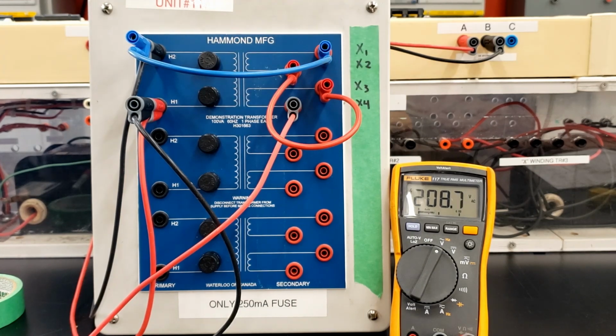This is probably the worst case scenario for a student. It's better when the primary and secondary voltages are additive, so we see them adding together on the meter — but that's clearly not the case here. So how are we going to fix this? Let me stop for a second and show you a diagram of what I've connected, and then you'll see why this reads 208 volts.